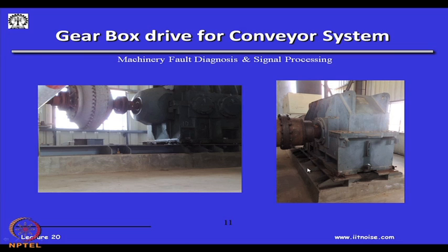Imagine, 100 feet or 100 meters above the ground, you are doing such an arrangement, and how do you ensure that they are all aligned? These are provisions where shims can be used. And to ensure that the vibration levels are less than the levels allowed as per the ISO standard, we have to monitor at all these possible locations, 18 locations in this case, 18 into 3, 54 channels, and see what the highest levels are and whether they qualify for the vibration standard.